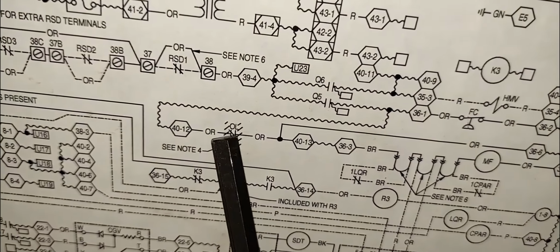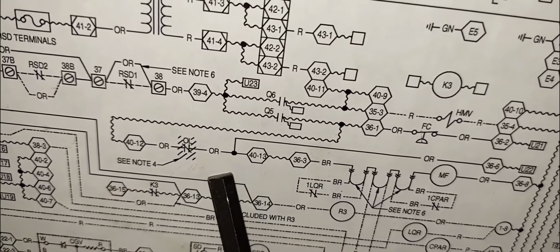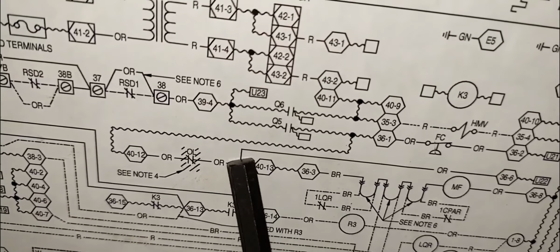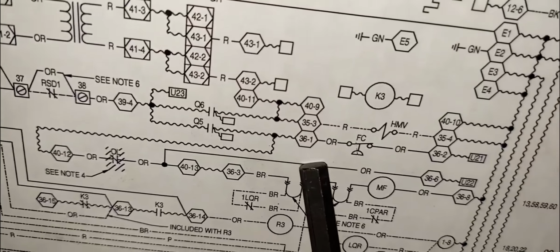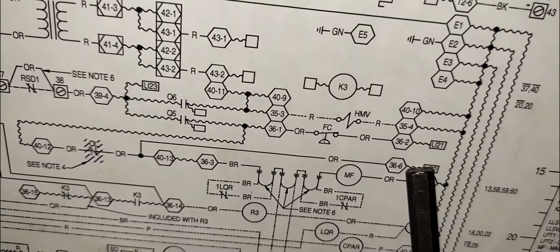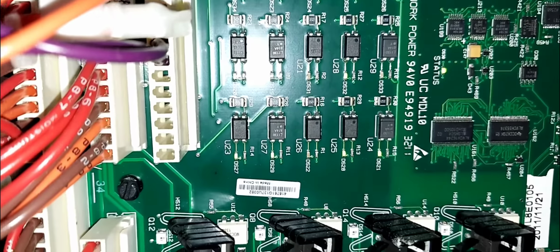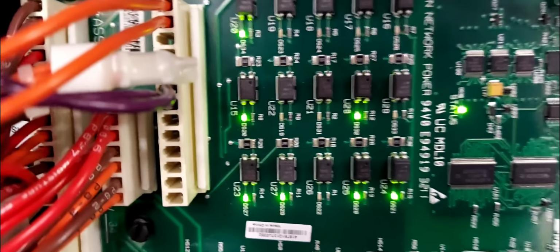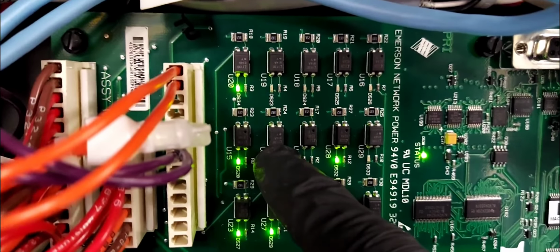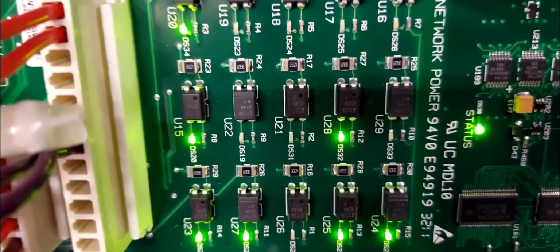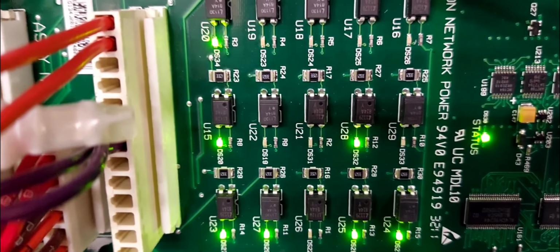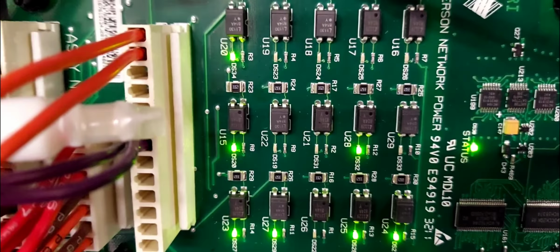There's another safety in line. So the 24 volts stops right here, because if it didn't, it would have passed. It would have got to this splice or connection, and then also now my U22 on the board would be lit. So U22 is right here. And as you can see, U22 is not lit. So there's no 24 volts power right there. Hence the reason why this board is in alarm. Okay? The unit is in alarm for the main fan failure.